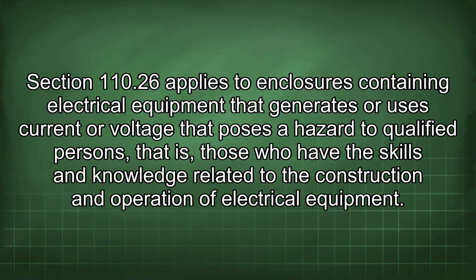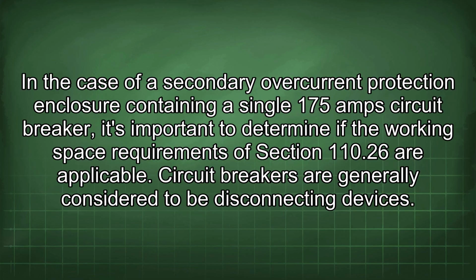Section 110.26 applies to enclosures containing electrical equipment that generates or uses current or voltage that poses a hazard to qualified persons, that is, those who have the skills and knowledge related to the construction and operation of electrical equipment. In the case of a secondary overcurrent protection enclosure containing a single 175 amp circuit breaker, it's important to determine if the working space requirements of Section 110.26 are applicable.